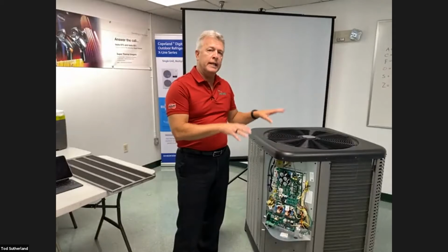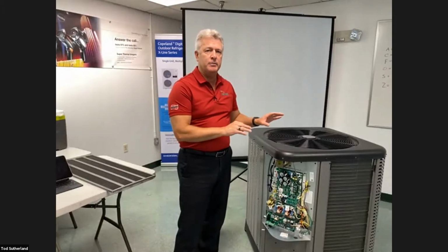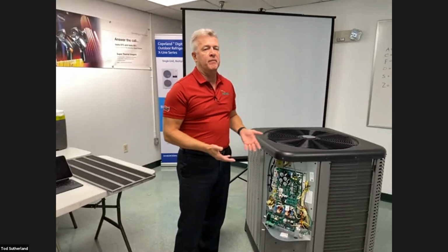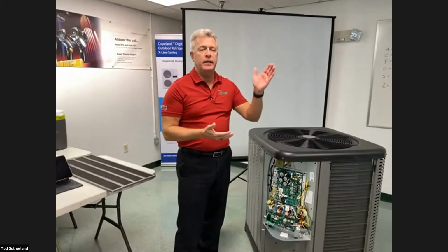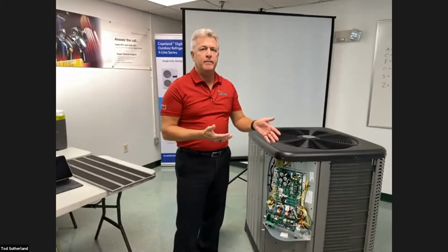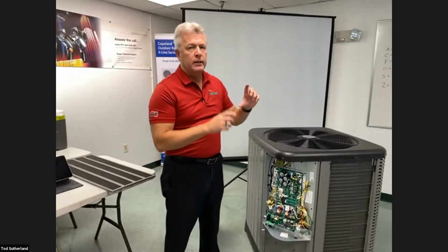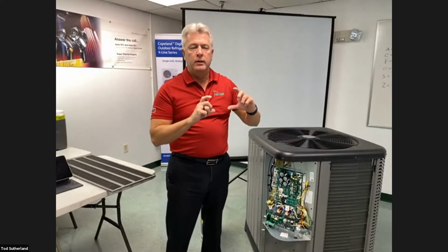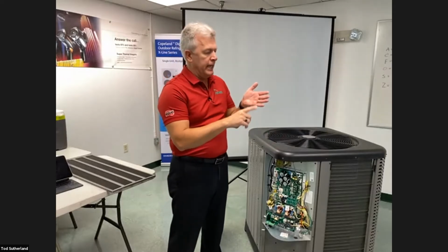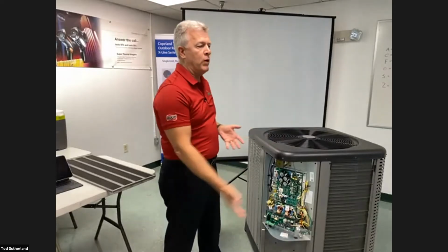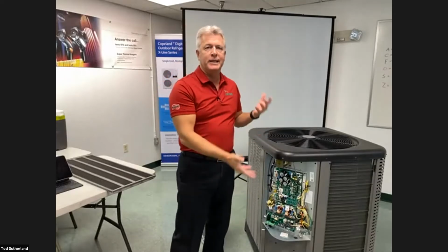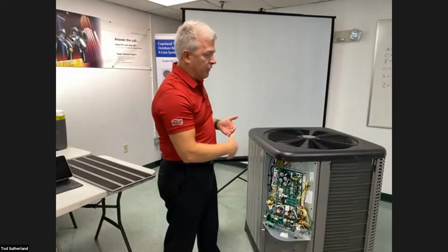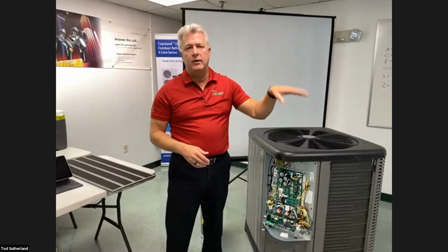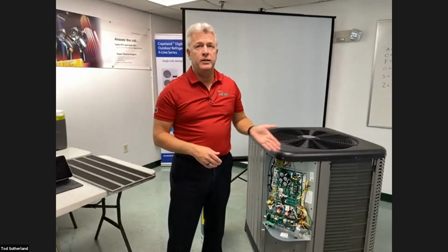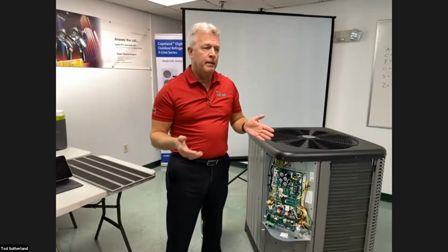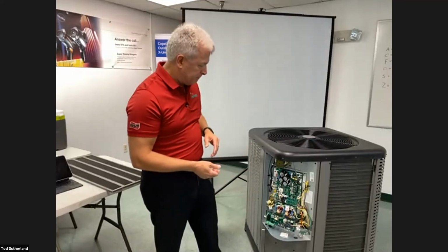It's a very important thing that when you're making these adjustments, you have the fan at full capacity, the condensing unit and the indoor blower at full capacity. Now, there's a charge feature in the Econet controller where you'll go into the system and hit the button for charging, and it will ramp both systems to the appropriate settings. They want your indoor airflow design on the air handler to be between 375 and 450 CFM. So make sure that you account for that.